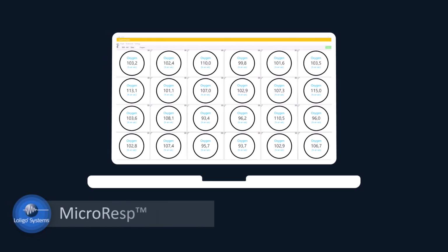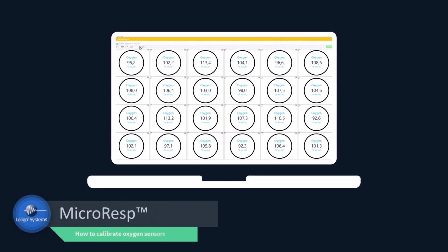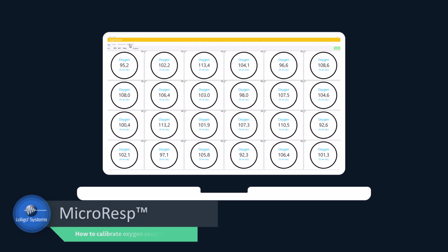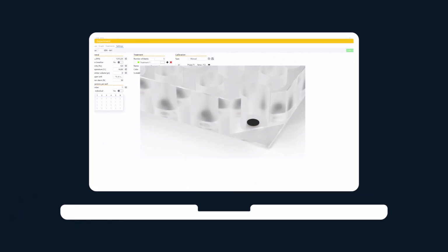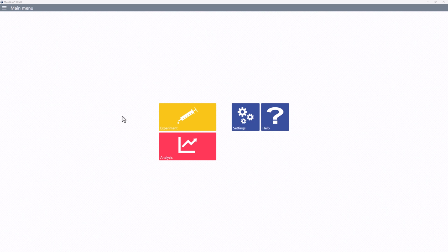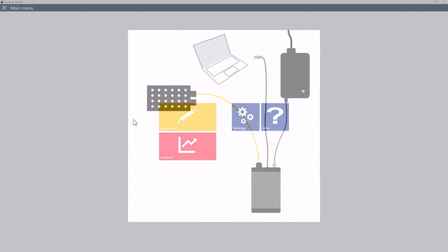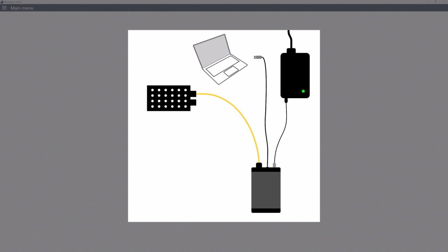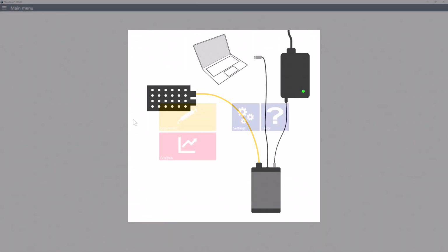When you want to run your first microplate respirometry experiment in MicroResp, you must first calibrate the oxygen sensor spots mounted on the floor of each well to get accurate oxygen readings. Calibrating the oxygen sensors can be done in the Settings tab in the Experiment menu, but before entering, a microplate reader must be powered on and connected to your PC via USB.